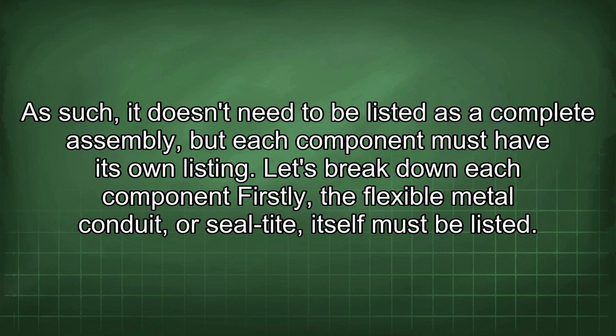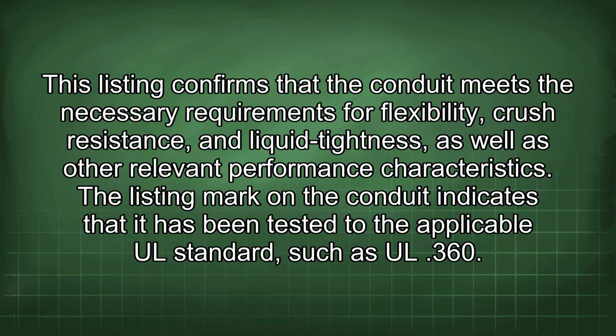Let's break down each component. Firstly, the flexible metal conduit, or Seal-Tite, itself must be listed. This listing confirms that the conduit meets the necessary requirements for flexibility, crush resistance, and liquid tightness, as well as other relevant performance characteristics. The listing mark on the conduit indicates that it has been tested to the applicable UL standard, such as UL 360.